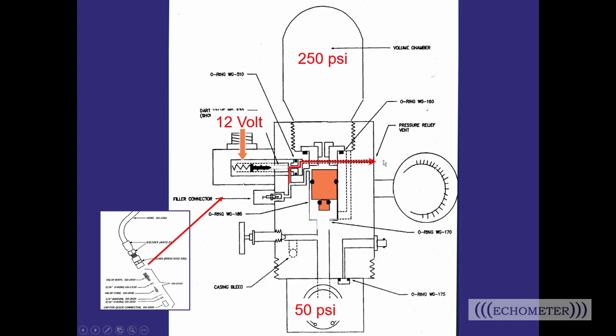And there's a tiny little hole on the side of your remote fire guns. You've probably seen that. And so that's a little pressure relief hole. And so that little bit of pressure from on top of the gas valve is released out that hole, which allows the gas valve to come off the seat. And so now all of that pressure in the volume chamber can leave the gun.